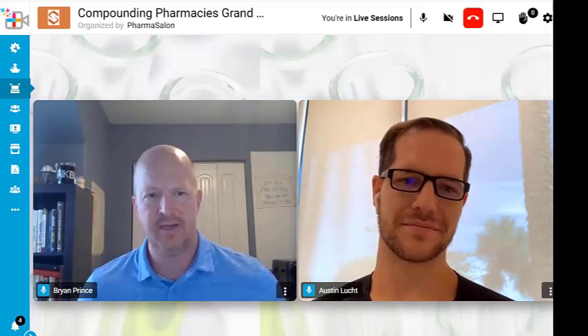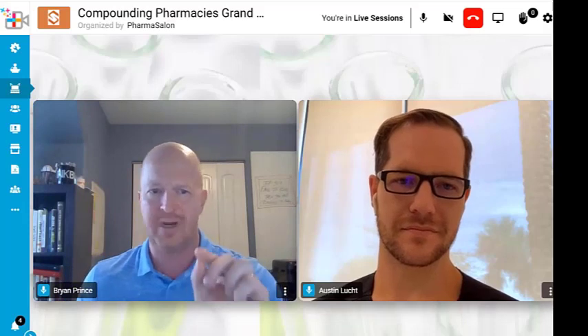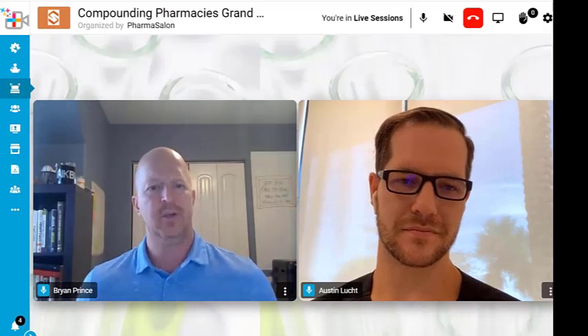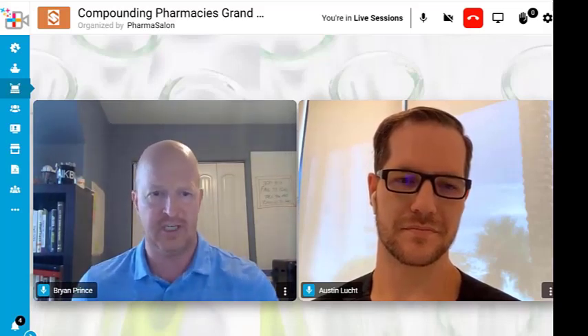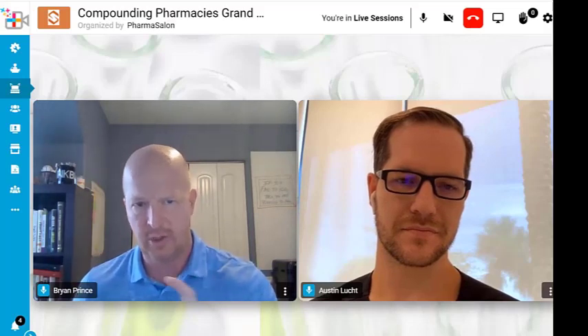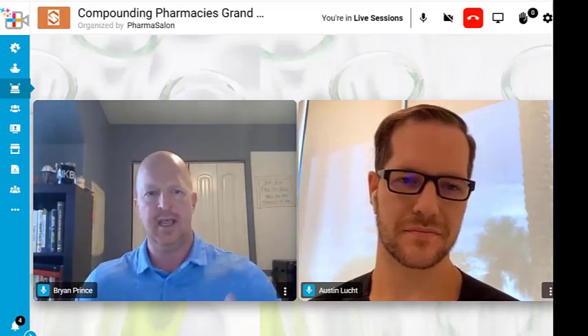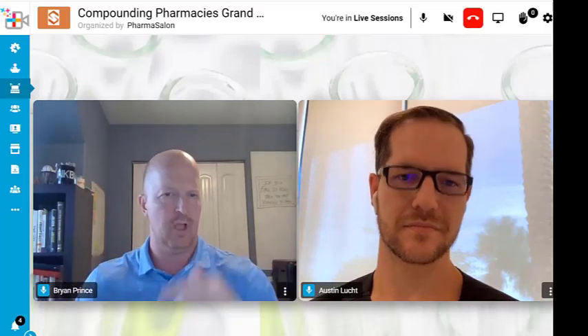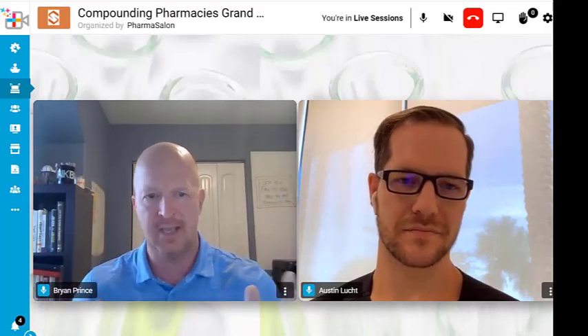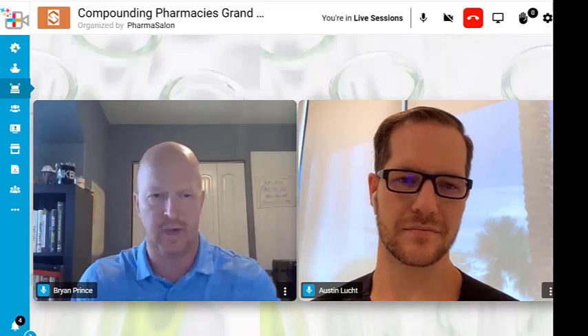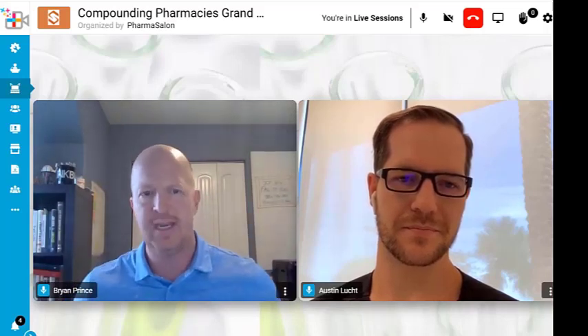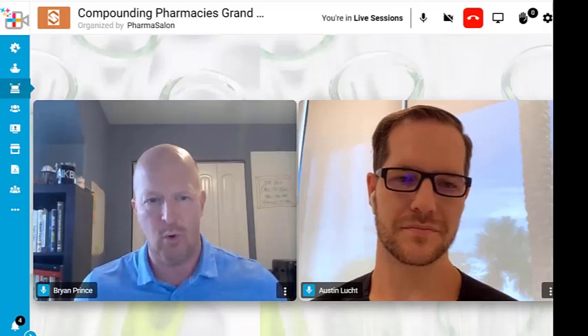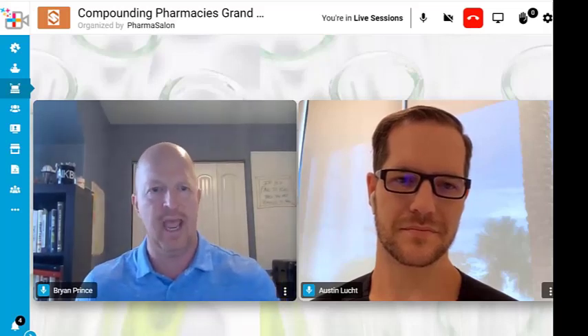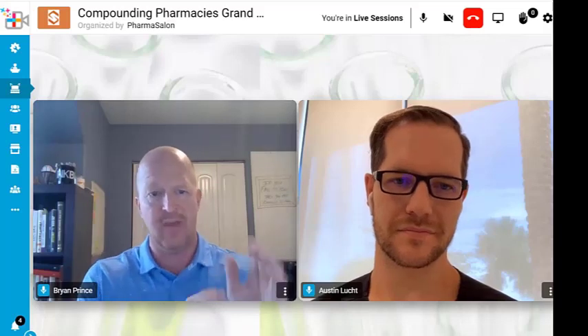So USP 797 says that we should, and really, even though it says should, a lot of state boards are going to hold that 20C to a strong must. And we know that at 68F, right? So some will say, well, we're going to spec out this air handling equipment at 68 degrees Fahrenheit, to which I would say, no, you do not. Because by the time you put a technician in a rear tying gown, double gloves, double shoe covers, hair bouffant, and mask, and they're wearing that 5 to 7 to 8. Of course, I don't know, your sterile gowns are probably very expensive these days. They're sweating at 68F. And so really you would want to spec out that new air handling unit at 64 to 65F as your target temperature.